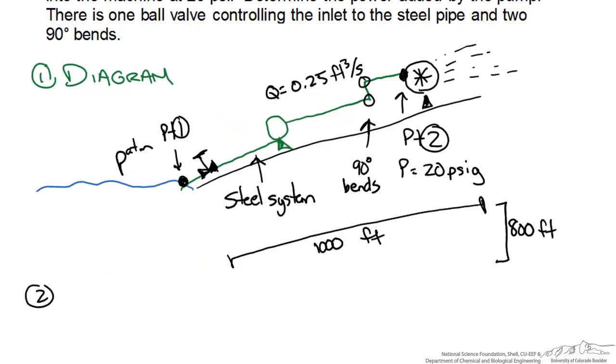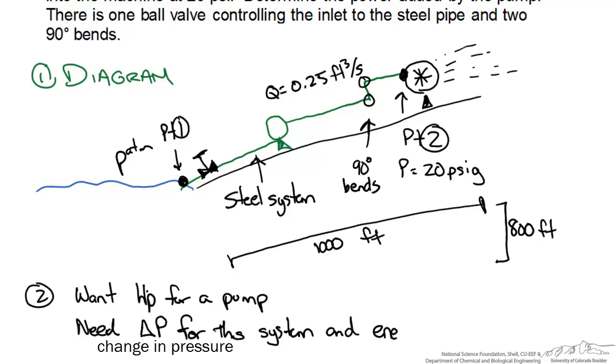This leads us to write down what we want: the horsepower for our pump. With any experience of problems like this, we know that means we need delta P for the system and energy losses. Power for a pump equals the shaft head for the pump, the specific weight of the fluid, and the volumetric flow rate. We already have two pieces of that information and just need to find the shaft work.